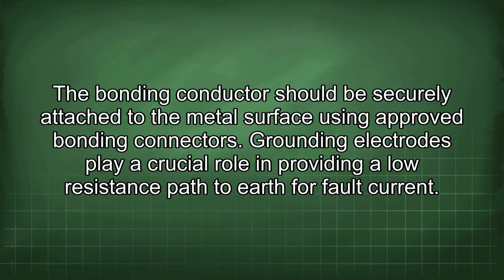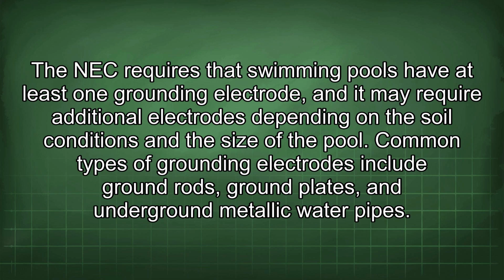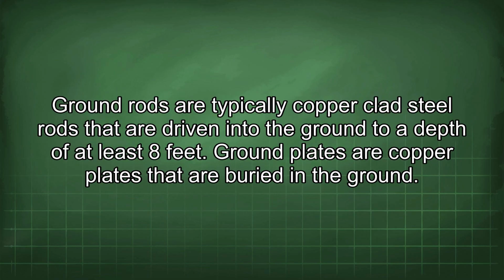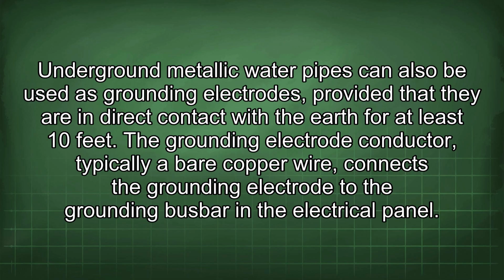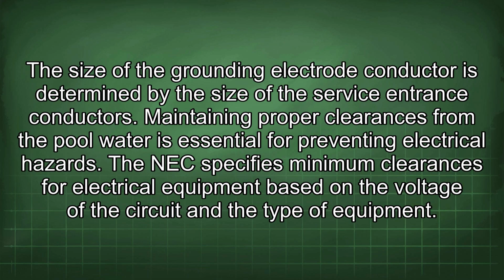Grounding electrodes play a crucial role in providing a low-resistance path to earth for fault current. The NEC requires that swimming pools have at least one grounding electrode, and it may require additional electrodes depending on the soil conditions and the size of the pool. Common types of grounding electrodes include ground rods, ground plates, and underground metallic water pipes. Ground rods are typically copper-clad steel rods that are driven into the ground to a depth of at least 8 feet. Ground plates are copper plates that are buried in the ground. Underground metallic water pipes can also be used as grounding electrodes, provided that they are in direct contact with the earth for at least 10 feet. The grounding electrode conductor, typically a bare copper wire, connects the grounding electrode to the grounding busbar in the electrical panel. The size of the grounding electrode conductor is determined by the size of the service entrance conductors.